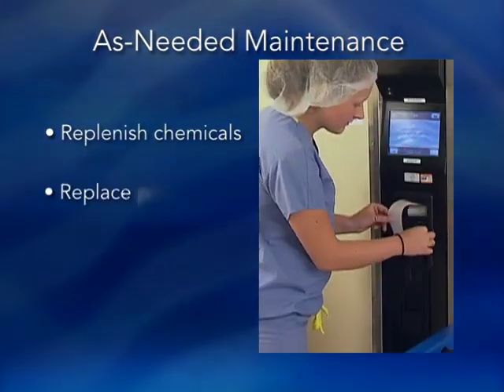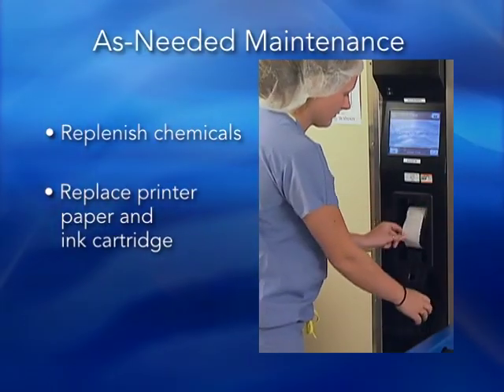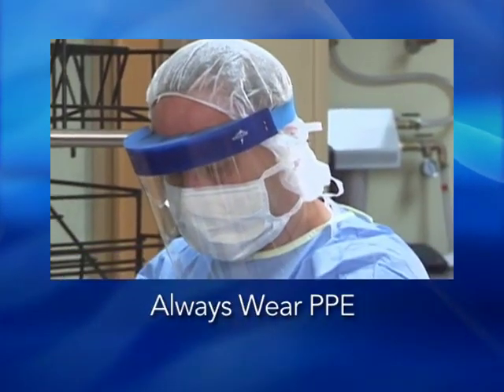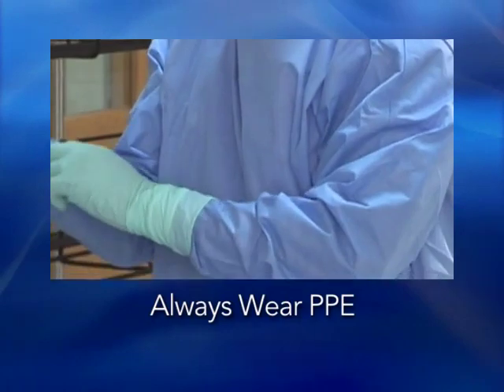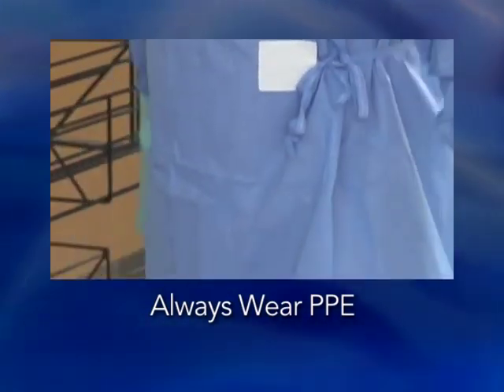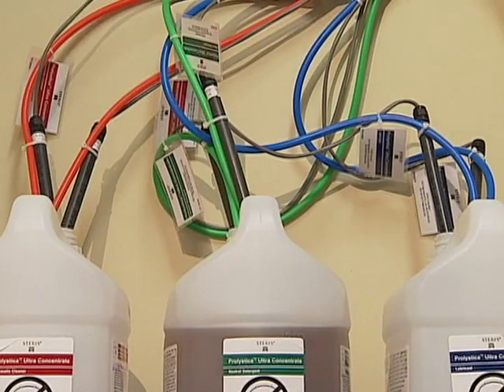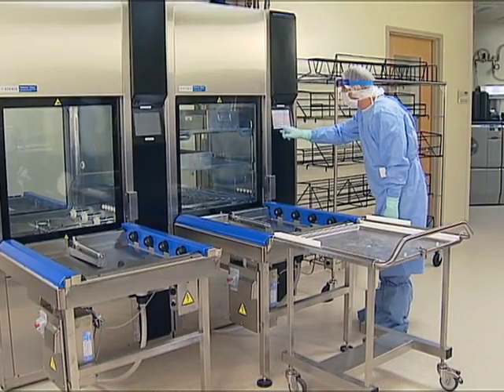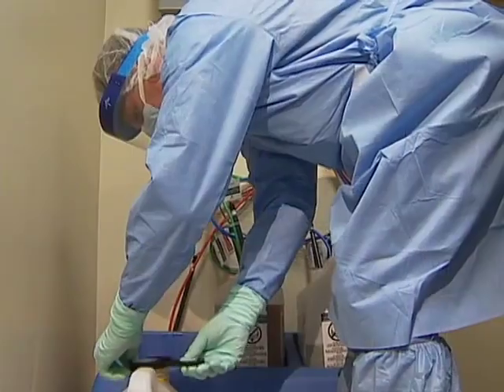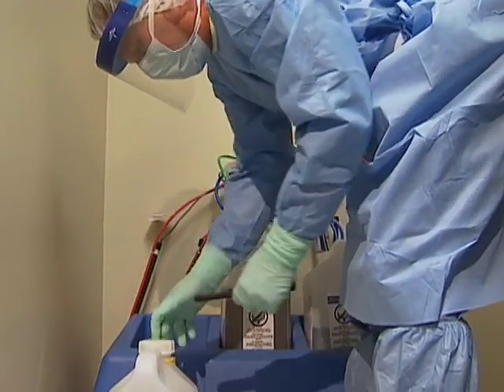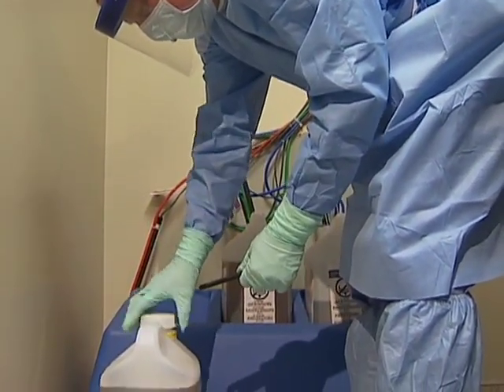This includes replenishing the processing chemicals and replacing the printer paper and ink cartridge. To replenish a chemical container that is low or empty, first be sure to wear your personal protective equipment. When it's time to change the chemistry, the low-level sensor will trigger an alarm, indicating when the chemical levels are too low. Open the new container and set it in close proximity to the container you're going to replace.